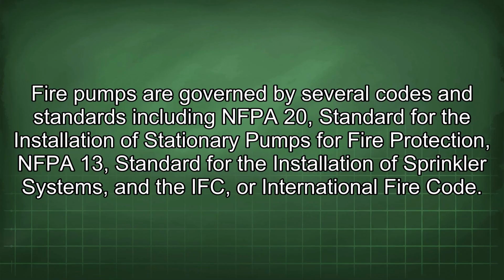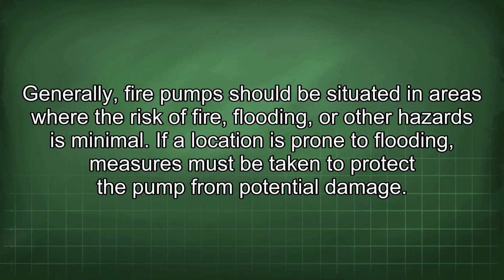Fire pumps are governed by several codes and standards including NFPA 20, standard for the installation of stationary pumps for fire protection, NFPA 13, standard for the installation of sprinkler systems, and the IFC, or International Fire Code. Generally, fire pumps should be situated in areas where the risk of fire, flooding, or other hazards is minimal. If a location is prone to flooding, measures must be taken to protect the pump from potential damage.